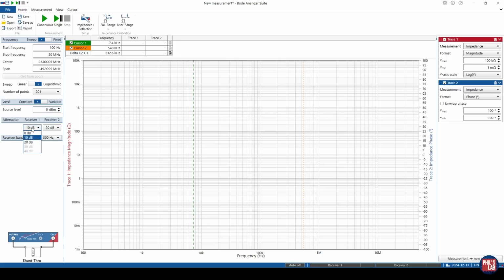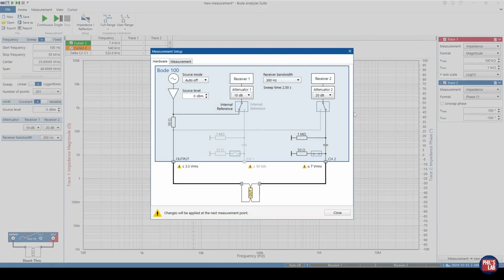The attenuators are for receiver 1 and receiver 2, and to see what they are, we can go to the impedance reflection setup at the top, and we can see this is actually how the Bode 100 is configured. So the attenuators are attached before receiver 1 and receiver 2. Again, changing the attenuator will protect the receivers from overload, but it can also worsen your signal-to-noise ratio. So you want to choose them so you don't overload the receivers, or you want to choose the attenuators low enough to get maximum signal strength.